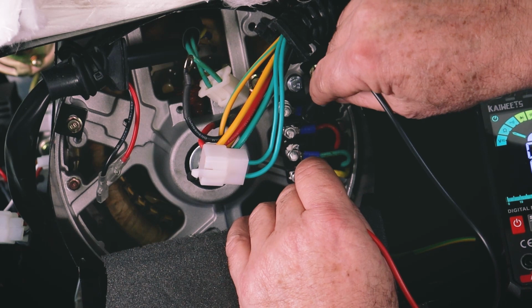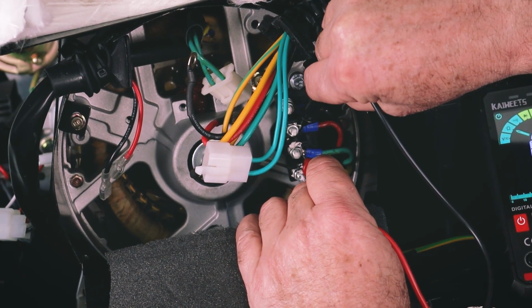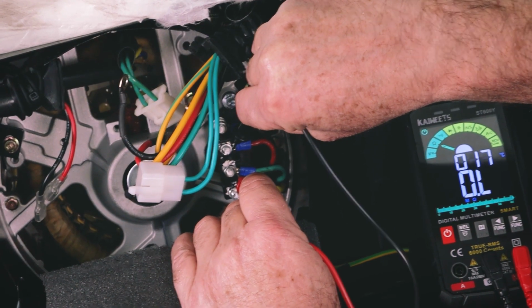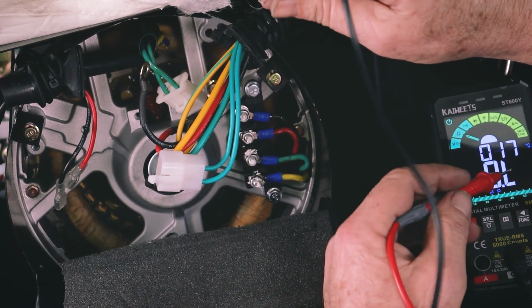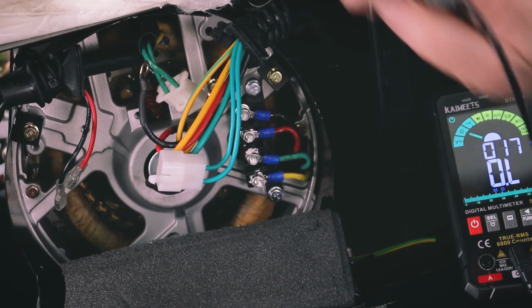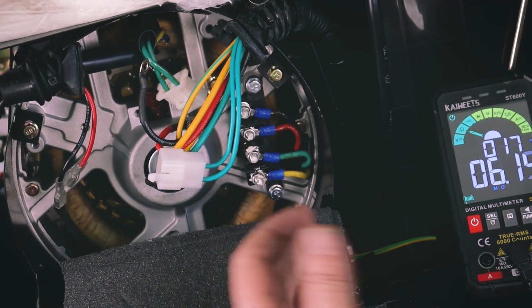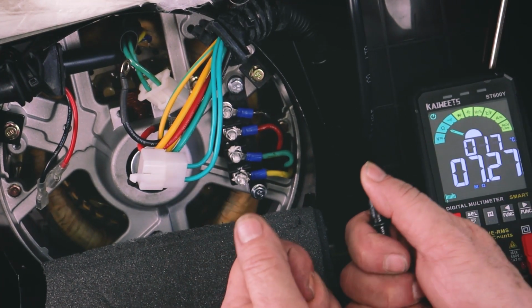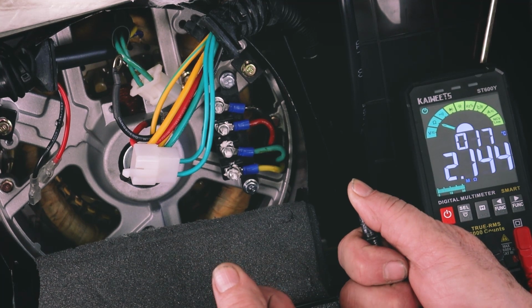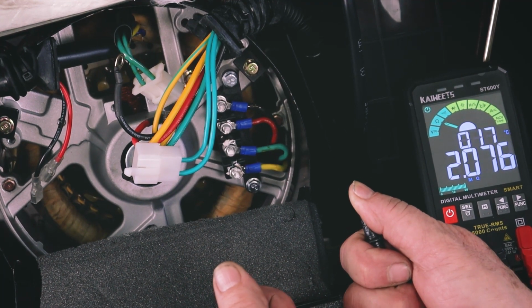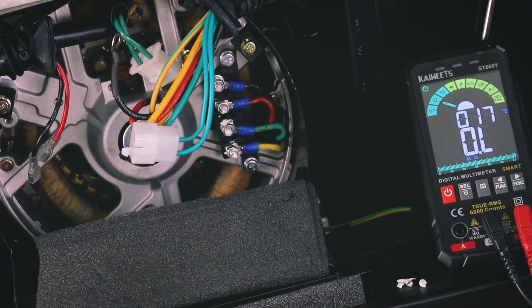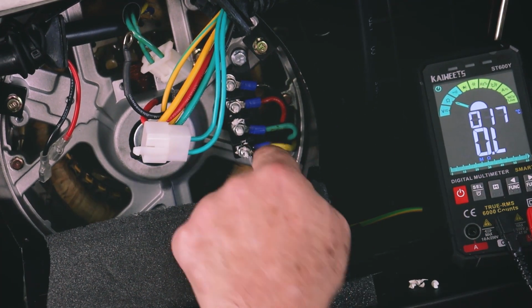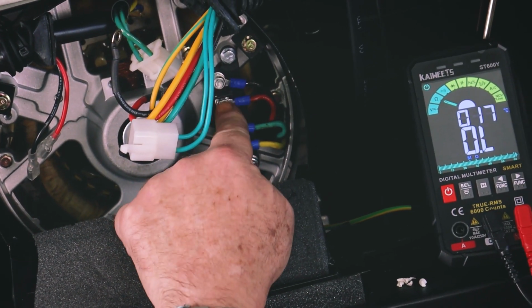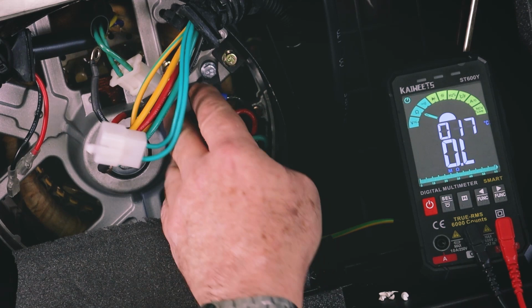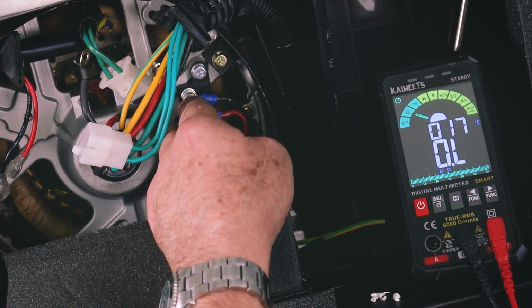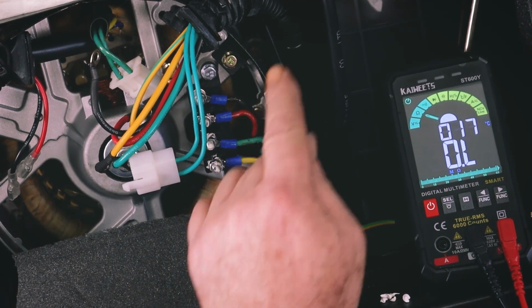So what we're looking for is, on my meter here, if I look at two windings that shouldn't be connected, is OL, no beep, over the limit, as it were. That pretty much means that we've got no connectivity. As you can imagine, if I touch my meter myself, my own body has, what have we got? 2.2 mega ohms, 2.1 mega ohms. Okay, so quite a lot of resistance, but it's not 0. So that's how we check those first of all. If they're coming in bad, we've got to change the alternator. If they're all coming in good, then we need to do the next check.